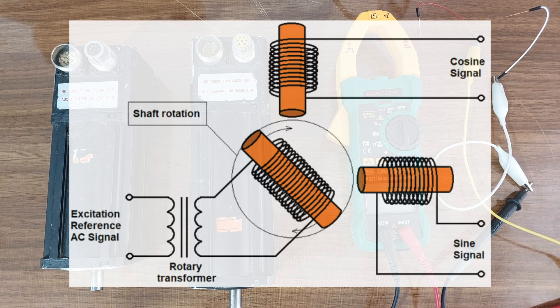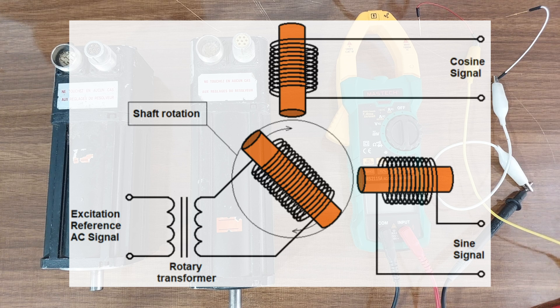The amplitude of the induced voltage in the sine coil and the cosine coil is a function of the rotor position. So by measuring the amplitude of the induced voltage in the sine coil and the cosine coil we can measure the rotor position. Later in this video we will measure the value of the induced voltages using the oscilloscope and also plot the trajectory that displays the rotor position.